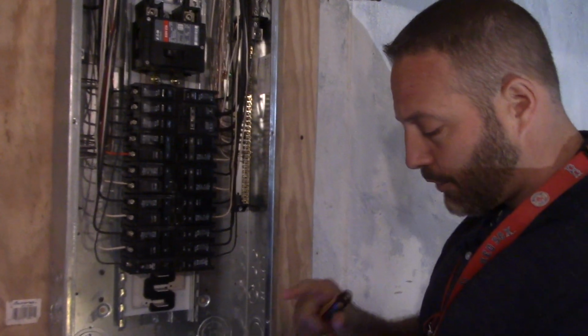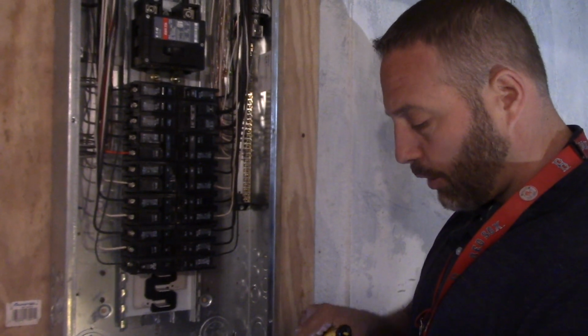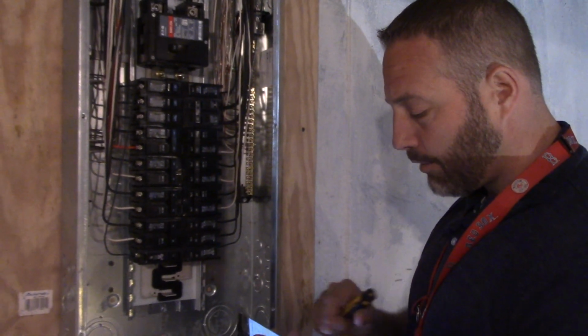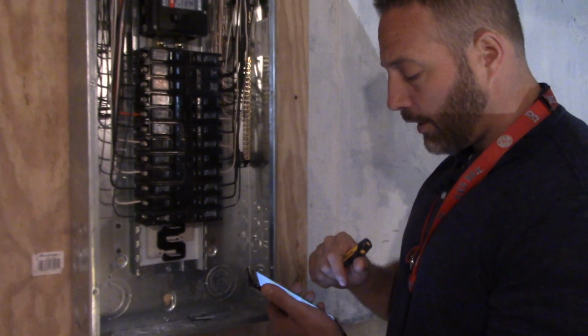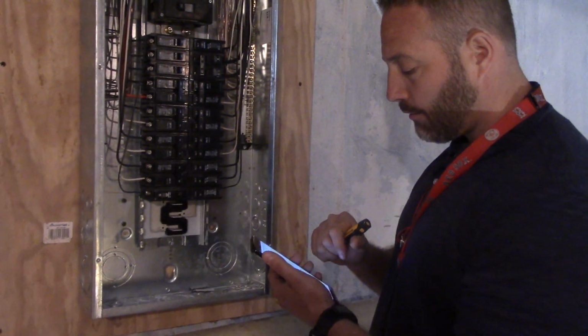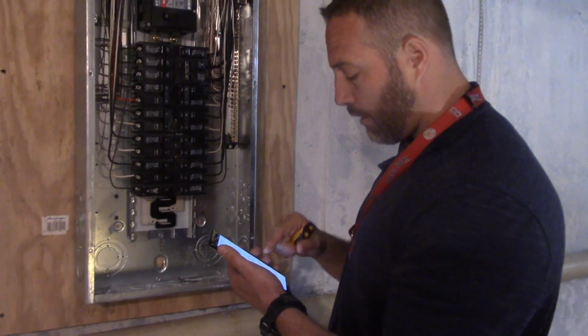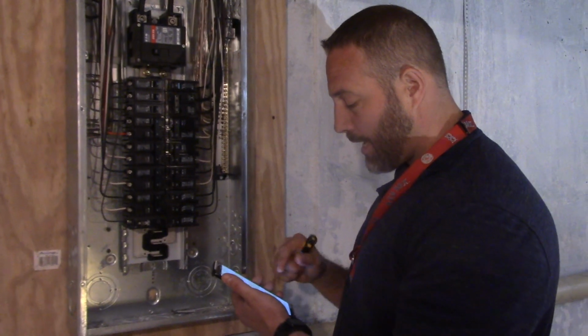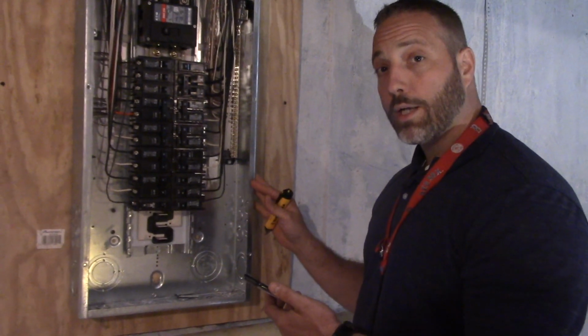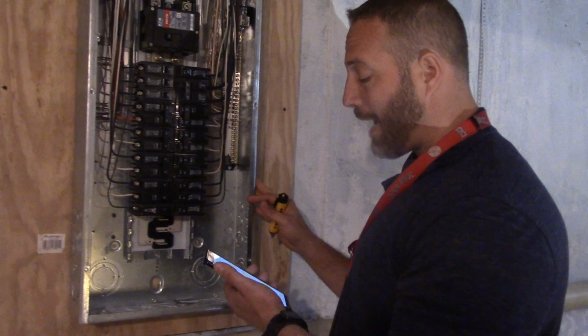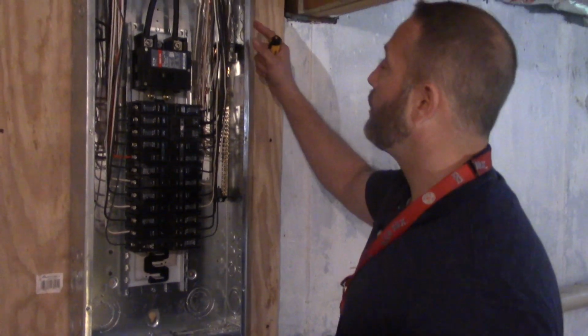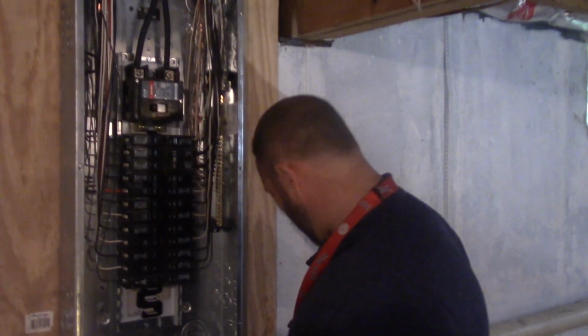So as we go back to our check sheet, we're going to identify for each of the breakers what the wire sizes were. So 15 amp was 14, 20 amp was a 12, 30 amp was a 10 gauge. Now once we do that, we're going to begin to look at the grounding. We want to follow this ground wire. So let's do that now.